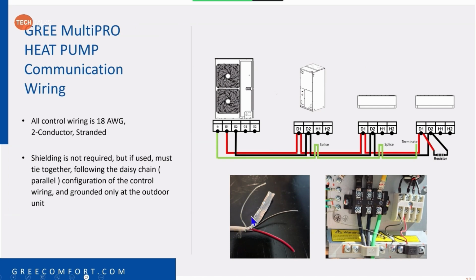That way, this ground and this aluminum shield, just tear it off of there. What we don't want is that ground to be able to touch anything in here. We don't want it to touch H1, H2, or anything. And then you carry that same pattern all the way through until you get to the last indoor unit. You do have to install this resistor that comes shipped with the outdoor unit. That is a 1/4 watt, 120 ohm resistor, and it's already got the little U channels on it for you to hook it up to D1 and D2. It just goes parallel to D1 and D2.